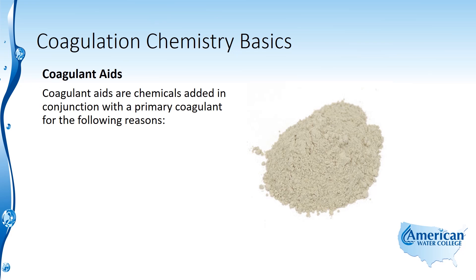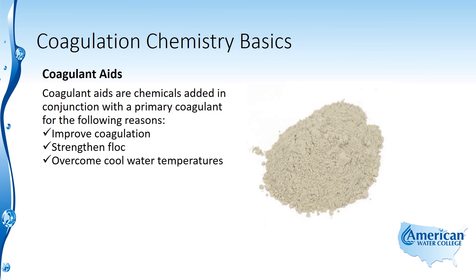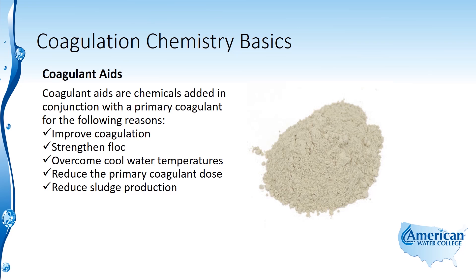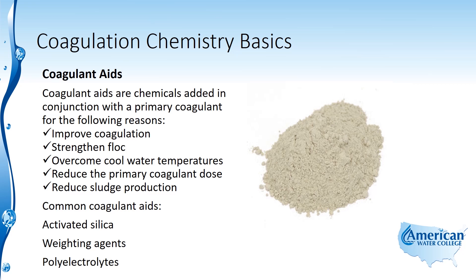We also add other chemicals to aid the coagulation process, and we call those coagulant aids. They are chemicals added in conjunction with a primary coagulant to improve coagulation, to strengthen the floc, to overcome cool water temperatures, to reduce the amount of primary coagulant required, and to reduce the production of sludge. The common aids used are activated silica, weighting agents, and poly electrolytes.